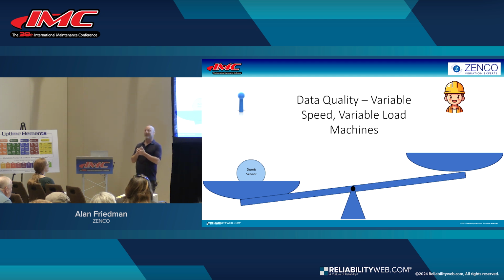A lot of the wireless sensors just wake up on a schedule, like once an hour, or once every 2 hours, or once every 15 minutes, take a reading, send it out, and go back to sleep. So a quick question: if you test a machine that's variable speed, one day at like 1,500 RPM, and the next time you test it, it's at 1,700 RPM, do you think it will vibrate differently? Does that mean there's something wrong with it?